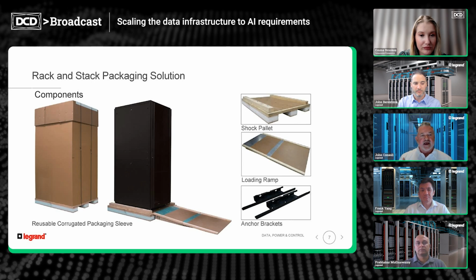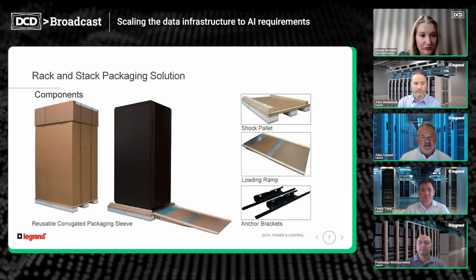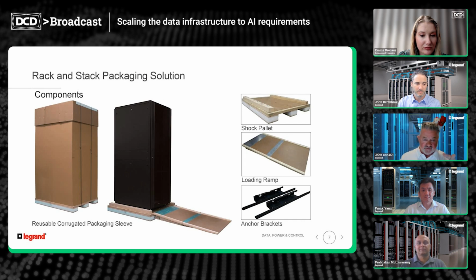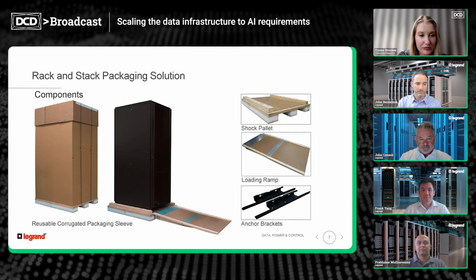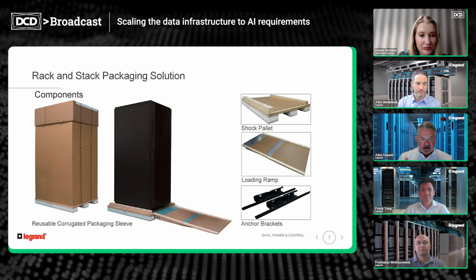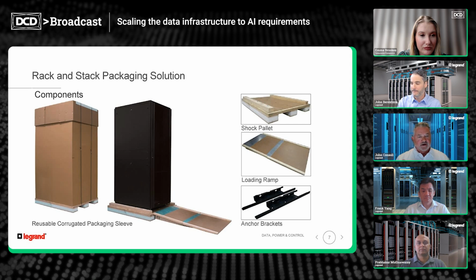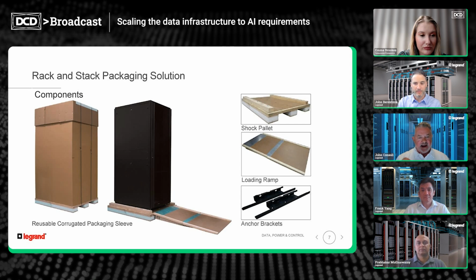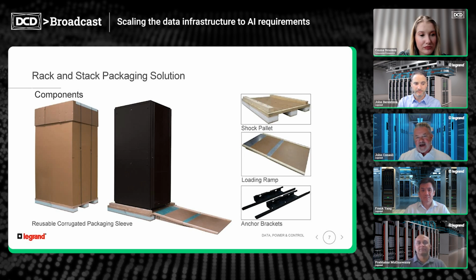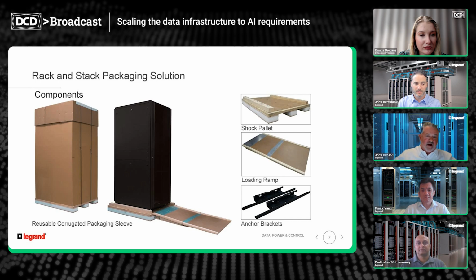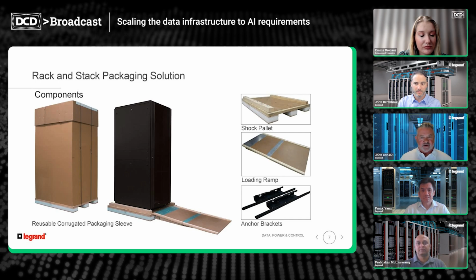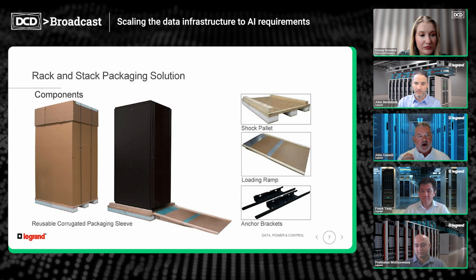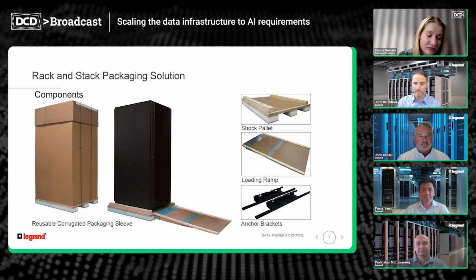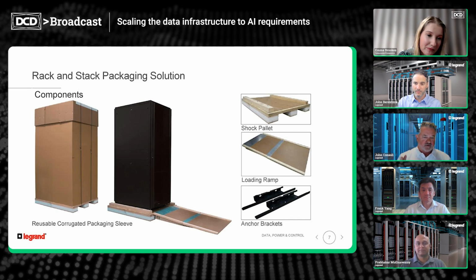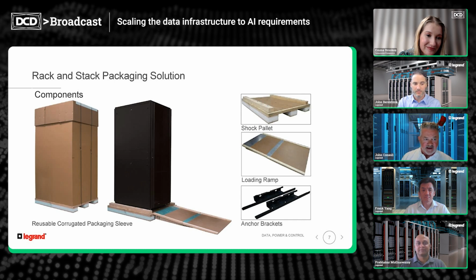The last thing, the E in FACE, is the equipment - by that we're talking about the manufacturer brand name. There really are no standards. When we hear GPU now, we automatically think of NVIDIA as the market leader. But when we talk about the actual system going into the enclosure, the equipment manufacturer can make a huge difference to the design of that rack - where the I/O is, front or back, how the racks interact with each other, whether there's inter-rack cabling needed. So keep in mind the equipment manufacturer, the OEM, and what their solution looks like, because that really impacts what the fully populated rack is going to look like. So that's FACE: three C's and an E.